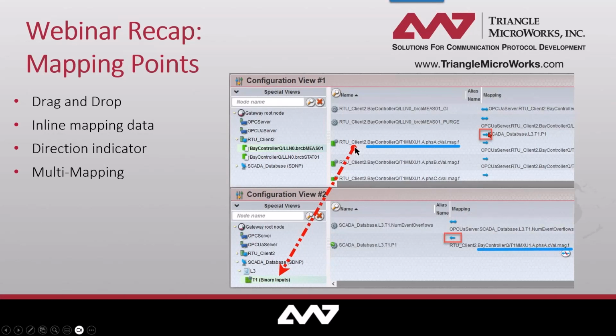We also added these direction indicators with red boxes around them, just to point that out as I put that in the PowerPoint. This lets you know which way the data is basically flowing - coming into our 61850 RTU client, and then that value is going out into the mapping to our SCADA database. Or from the other configuration view, you see that the value is coming into our SCADA database.